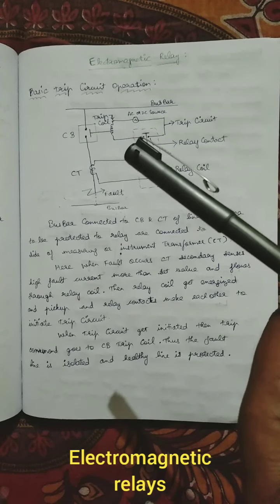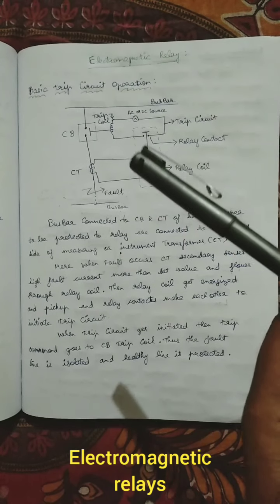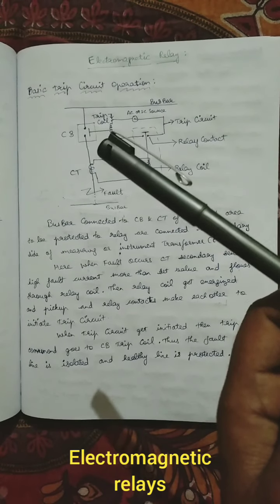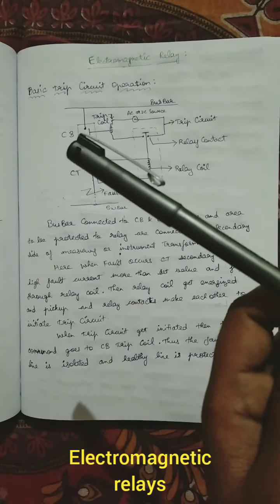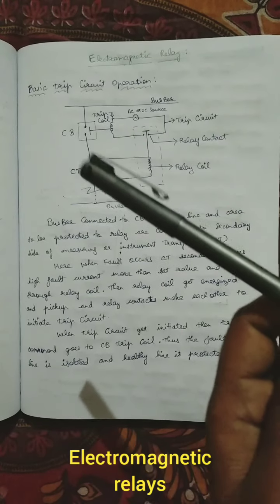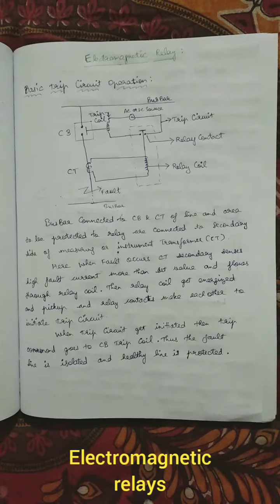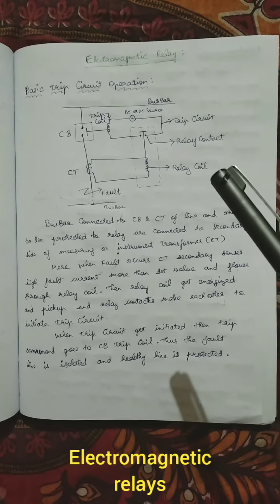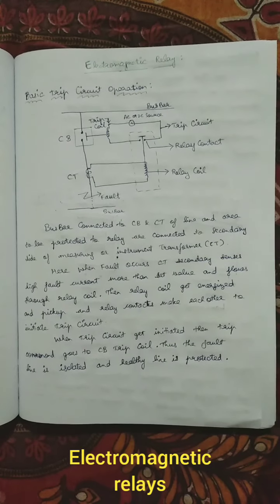For a DC source, one end is positive and the other is negative. When the relay contacts touch each other, a pulse is generated to the trip coil of the breaker, the trip is initiated, and the breaker opens. The faulty line gets isolated from the healthy line. This is the basics of a relay tripping circuit. Now we will go to electromagnetic relays.